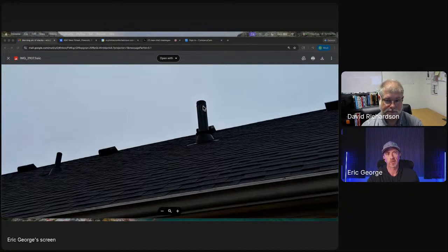So what happens, David, if there's not a cap? This is a metal flue pipe, not a PVC pipe. Looks like it goes to an 80% gas furnace or an older atmospherically vented water heater. If there's no cap, you're going to get water coming down the flue pipe, which eventually leaks out somewhere inside the house. I'm also wondering if this flue pipe might be going through the same bulkhead in the garage. There's a possibility. It's not ideal, but a lot of times those vents run horizontally in those chaseways and then go up through a vertical chaseway to get outside.